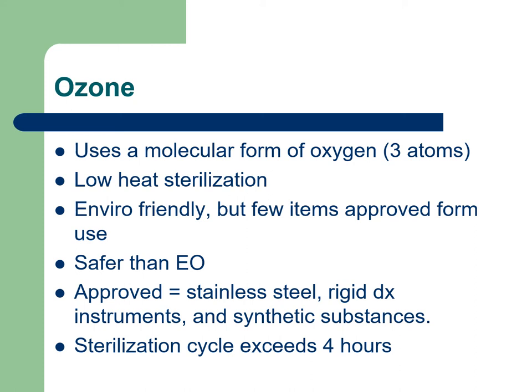Another example of a sterilant is ozone, which uses a molecular form of oxygen with three oxygen atoms. This is also used to filter air—a while back, ozone filters were all the rage for putting in your house to filter indoor air. It is very safe, doesn't leave any scary harmful residue, and doesn't put anything into the environment. It's also a good alternative to ethylene oxide for equipment and items that cannot withstand high heat and moisture, because ozone is a low heat sterilization process.